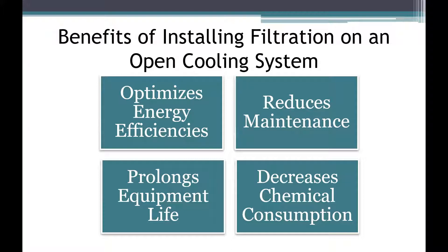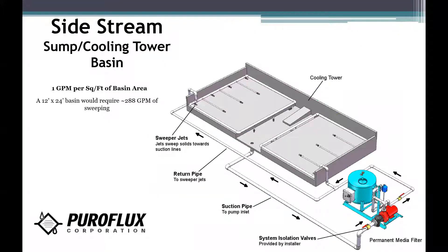So let's put a filter system on your tower. The first way we can do it is your typical side stream. Here we have a filter system with sweeper nozzles in the cooling tower basin. The rule of thumb for sizing for sweepers is 1 gpm per square foot of basin area. Using this as a guide, if we have a 12 by 24 basin, we're going to require around 288 gallons a minute of sweeping. Dirty water is brought to the filter, and filtered clean water is sent back to the basin via the nozzles.